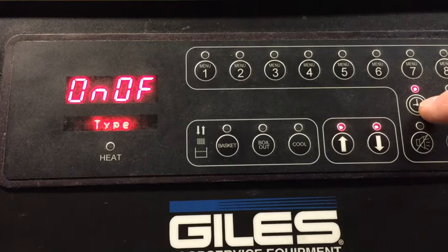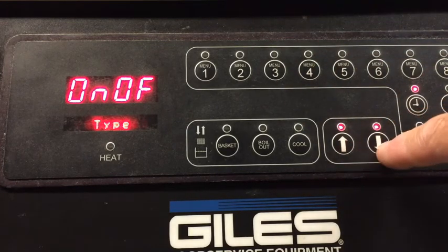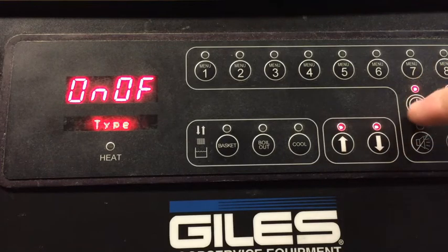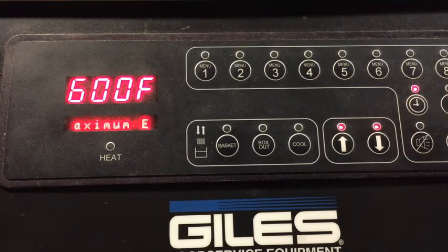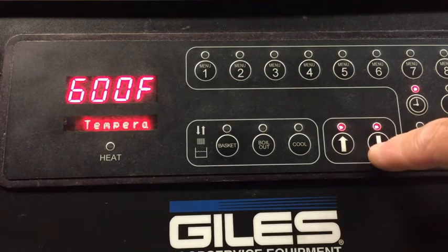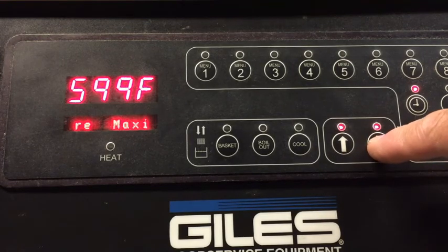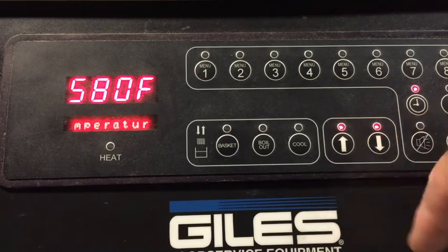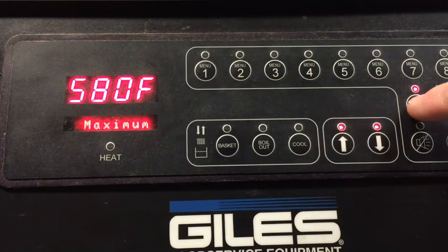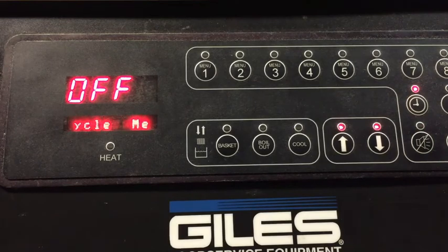Okay, you'll notice that the clock button is lit up. That means it's the only active key, besides the up and downs. So we're going to press the clock to advance to the next setting. Maximum element temperature, 600 degrees. Typically with the GEF, we're going to set that at 580. So let's go bring this down to 580. Okay, once we press the clock, we're going to save that setting and advance to the next.